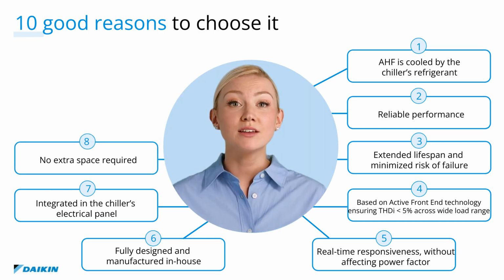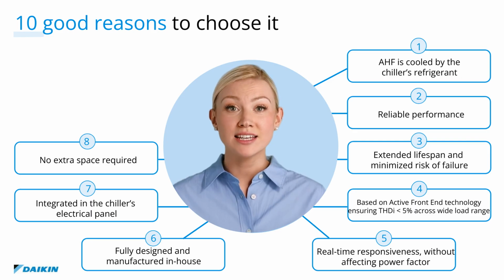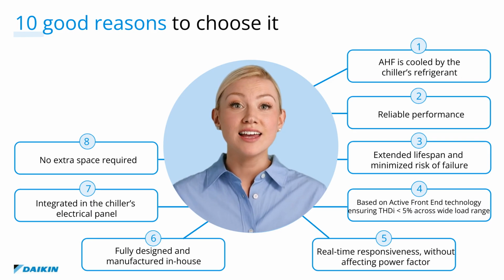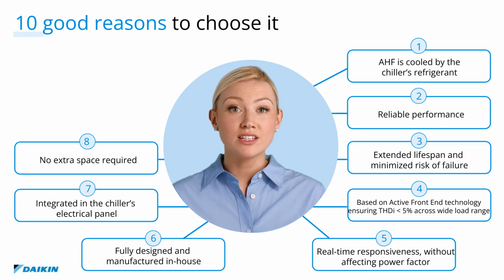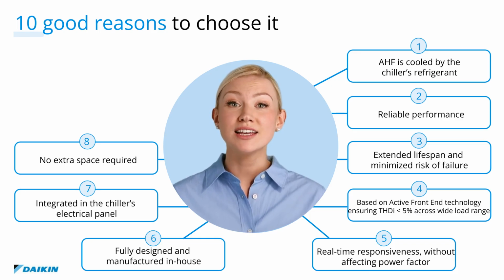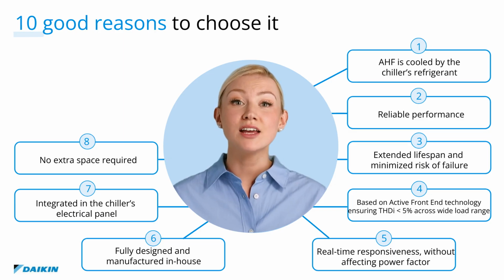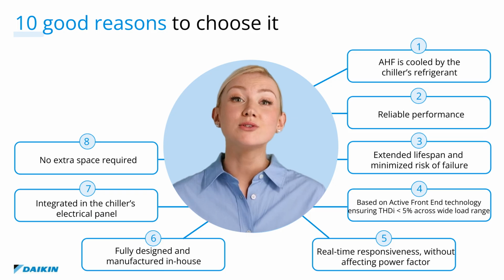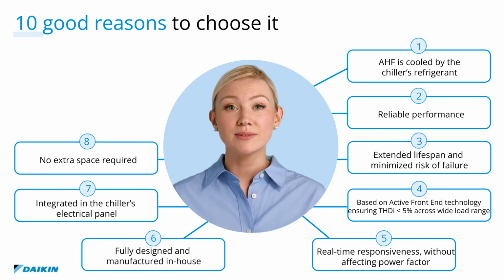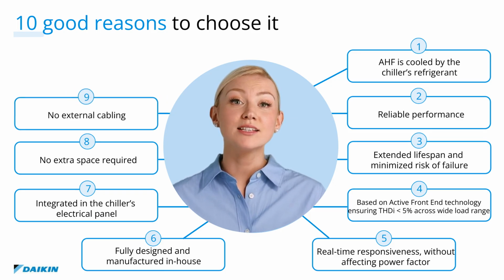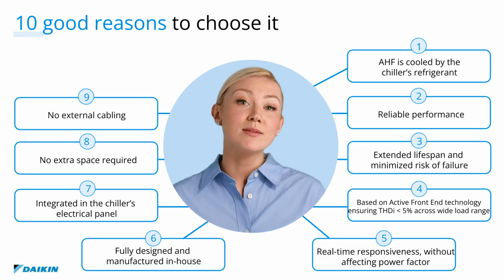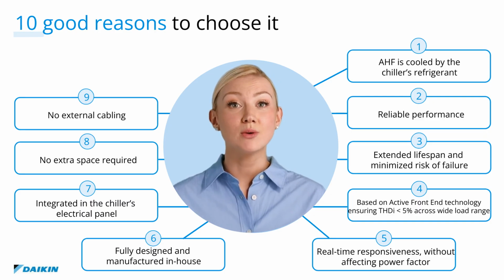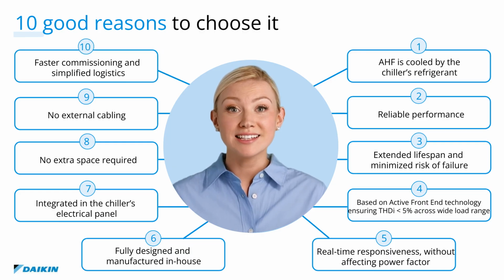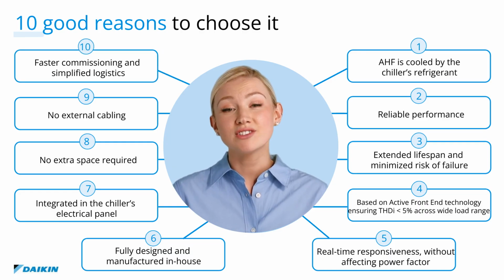To be more specific, when designing or retrofitting a data center, every square meter counts and every hour of on-site work has a cost impact. A compact integrated solution helps optimize the available layout, leaving more room for revenue-generating IT equipment. At that point, eliminating additional wiring simplifies installation, reducing potential points of failure. That makes a big difference in practice. Commissioning is faster, logistics are simpler, and overall installation costs come down.